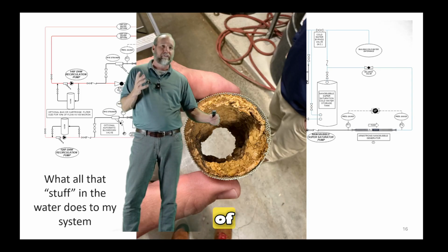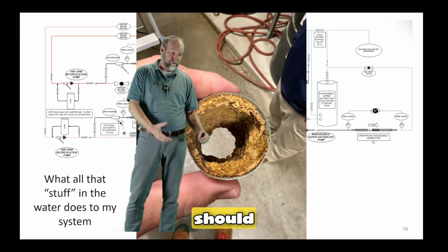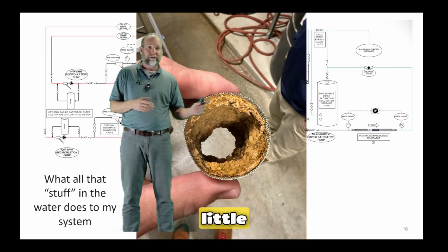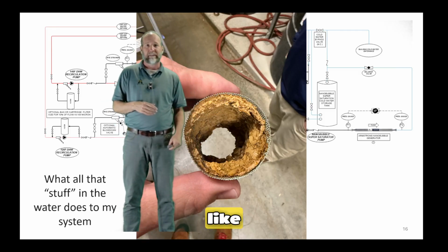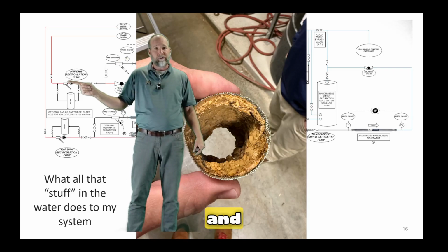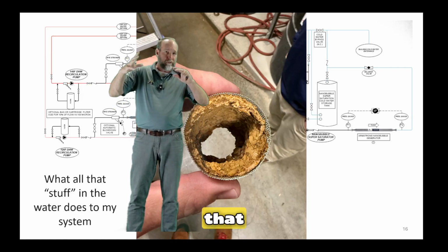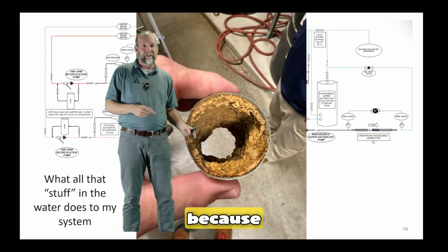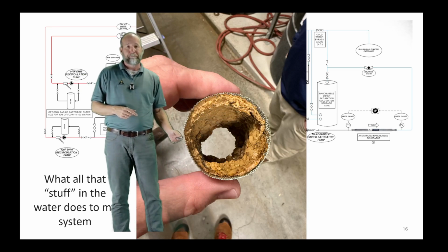40 pounds coming out of a garden hose is a pretty good stream. It should jump out of the drain. You should have to keep your foot on it. So if it's just kind of petering out a little bit, chances are you got something like that. But either way, go ahead and remove that basket, remove that bonnet, pull this screen out, and actually clean all of this out because this is bad news, okay?